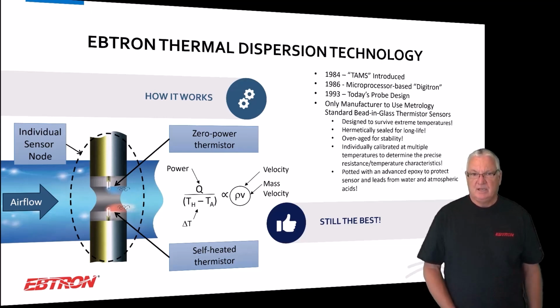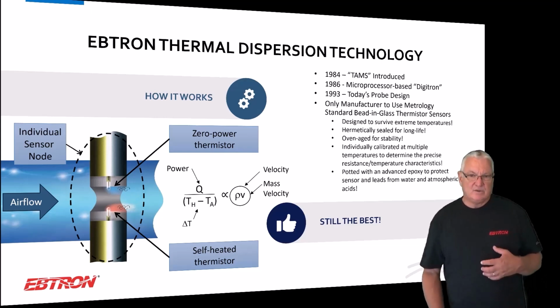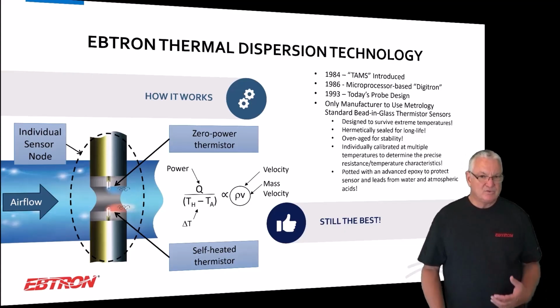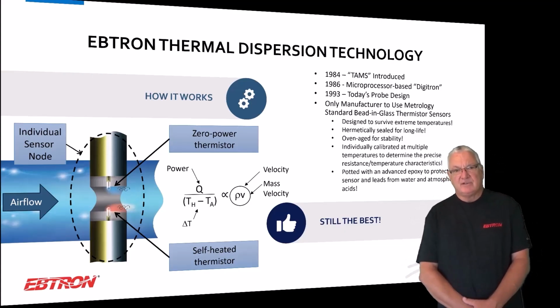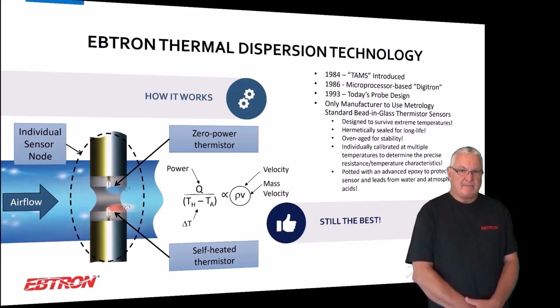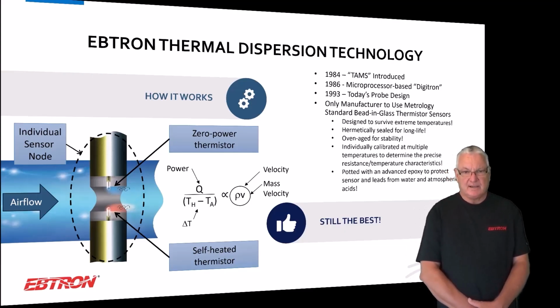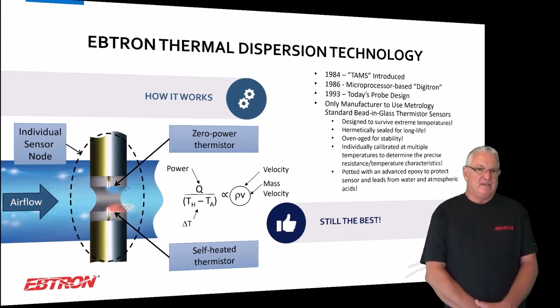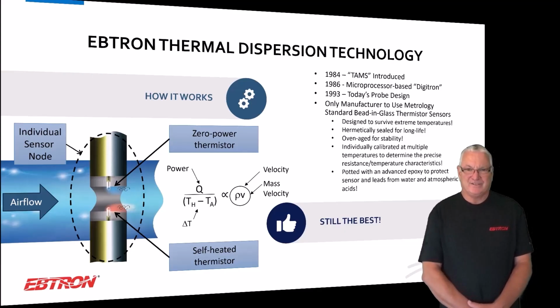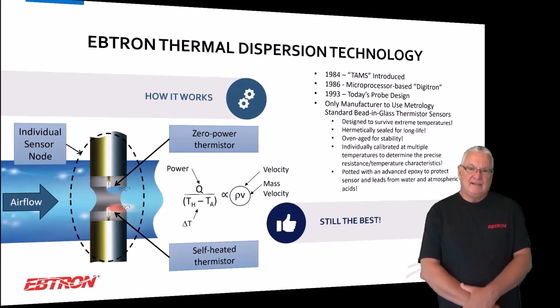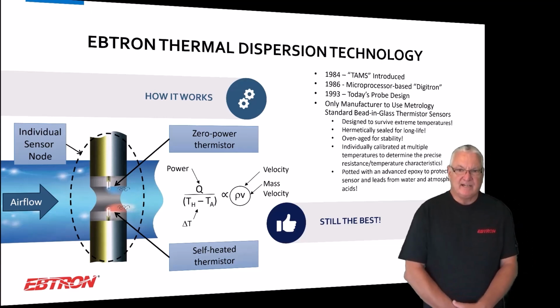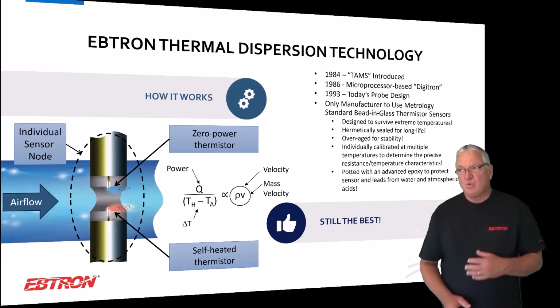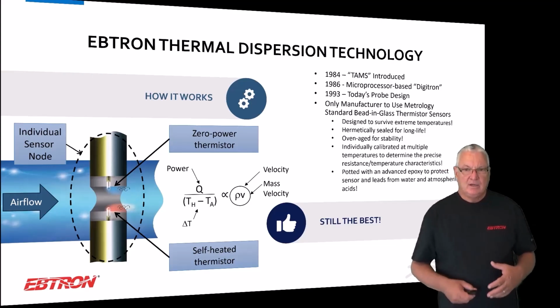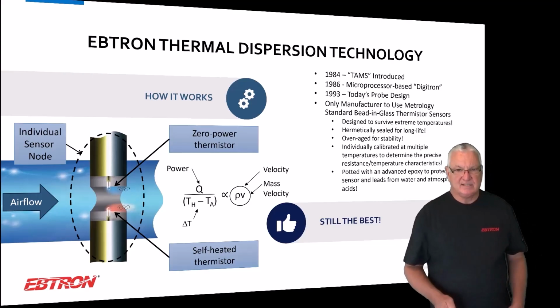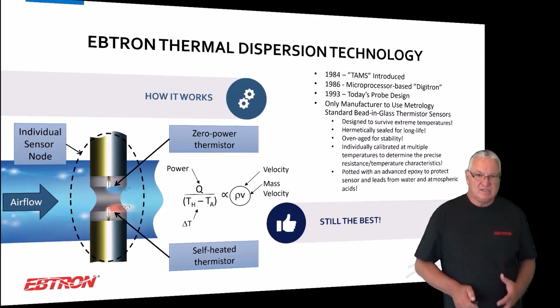It gives them stability. They are variable parts, so we have to take each one of them and put them in multiple controlled temperature circulating baths to get the resistance temperature characteristics. It's one thing that I think has kept people out of using this device. It's just not something you just walk off the street and say, I'm going to start doing bead glass thermistor thermal dispersion flow meters, okay? And then the sensor itself is potted in a marine grade epoxy, so it's waterproof. It's not affected by salt water or atmospheric acids. Okay, well, it's just a good design on the sensor node.